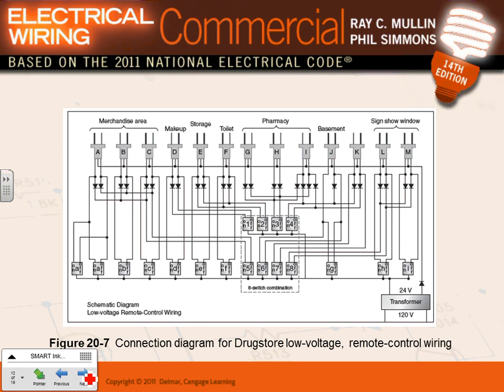This is the low voltage control system panel for the whole project that we have. Look how easy that is. Your start point is with the juice. Remember when I told you, Aaron, have you circuited the lighting control panel? You said, no, Chad, we're going to go circuit it. That's what you did. You gave a 20 amp circuit to this transformer, to juice it, right? Then that transformer will turn it into 24 volt. Now, I'm using only 24 volt for all of them.